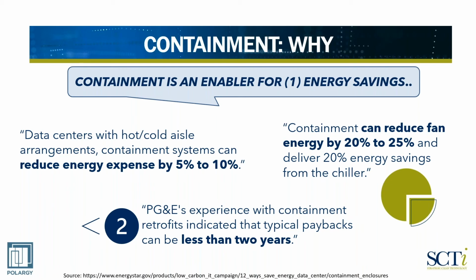And in our experience, of course, we're always looking at the cooling system. If you've got a chilled water cooling system, you're getting those savings because now you can increase the temperature of the water. You can increase the temperature set points on the CRAH units. You can reduce the number of CRAH units that are operating. And if your CRAH units are equipped with variable frequency fans or variable speed fans, you can reduce the airflow or reduce the fan speed typically by at least 20%, 30%, again, depending upon the site and on how well it's set up.